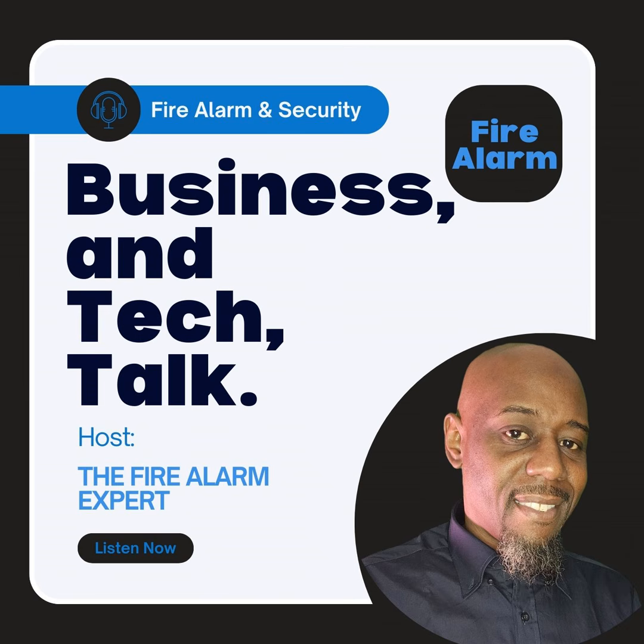For the alarm type, an alarm event activates when a specific point on the panel goes into alarm. If I'm using the point type or the device type, you see here it says alarm, smoke, and then level 1 smoke. Alarm is the input event, or the alarm event. Smoke is the actual qualifier. So when the smoke goes into alarm, what message, what label is attached to this smoke? Because if you have multiple smoke detectors, you're going to have multiple labels, and I'll show you what that looks like inside the objects label inside the SDU. So we're telling it on the input side that when this particular smoke with this label goes into alarm, we want some things to happen on the output side.